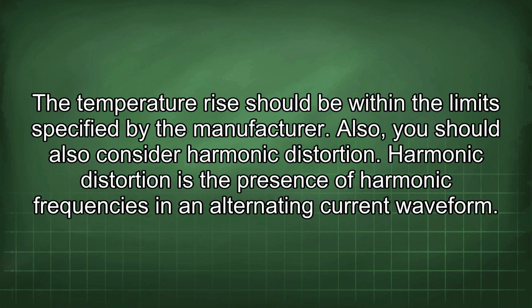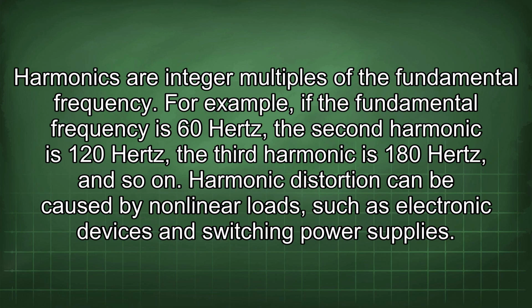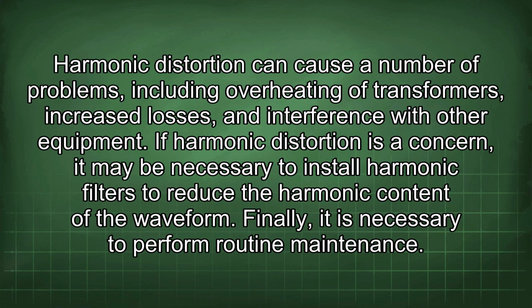Also, you should consider harmonic distortion. Harmonic distortion is the presence of harmonic frequencies in an alternating current waveform. Harmonics are integer multiples of the fundamental frequency. For example, if the fundamental frequency is 60 Hz, the second harmonic is 120 Hz, the third harmonic is 180 Hz, and so on. Harmonic distortion can be caused by nonlinear loads such as electronic devices and switching power supplies. Harmonic distortion can cause a number of problems, including overheating of transformers, increased losses, and interference with other equipment. If harmonic distortion is a concern, it may be necessary to install harmonic filters to reduce the harmonic content of a waveform. Finally, it is necessary to perform routine maintenance.